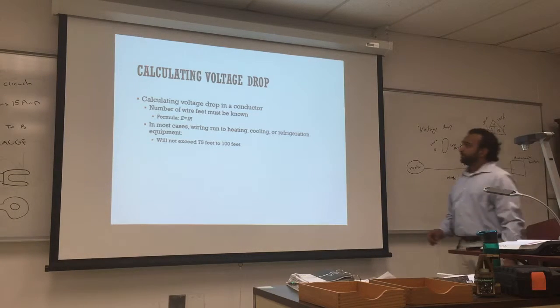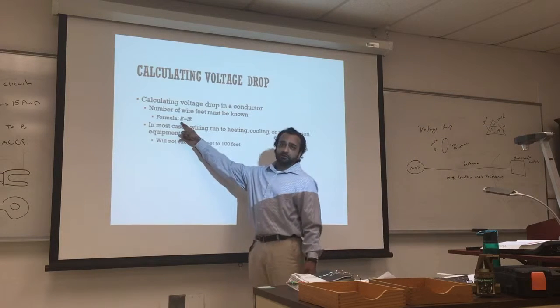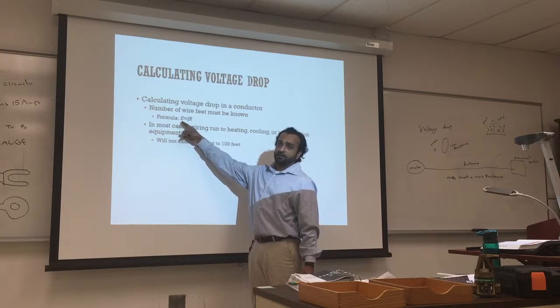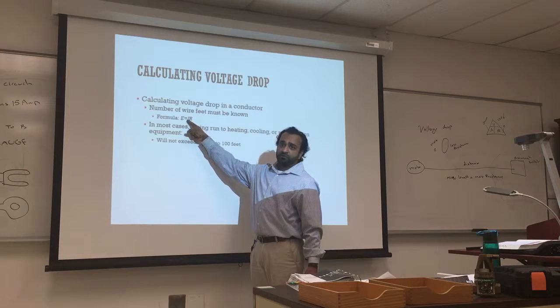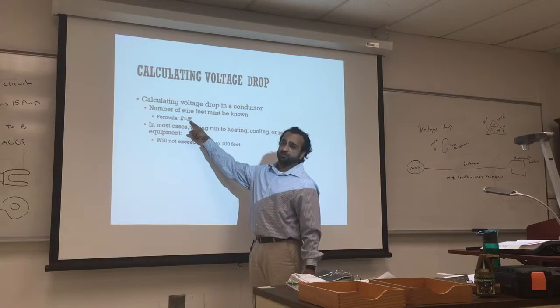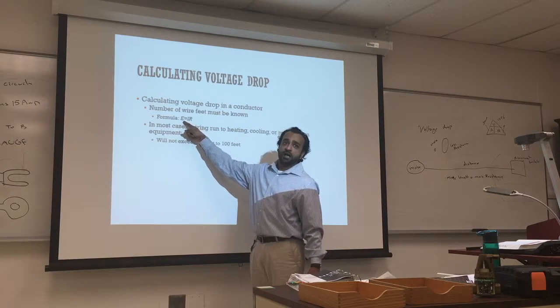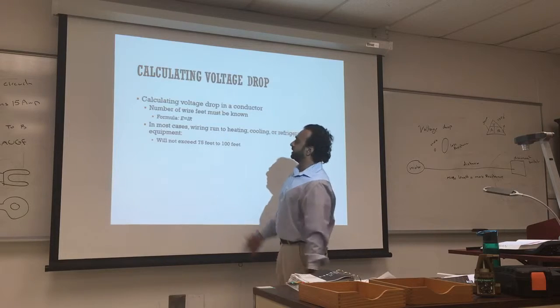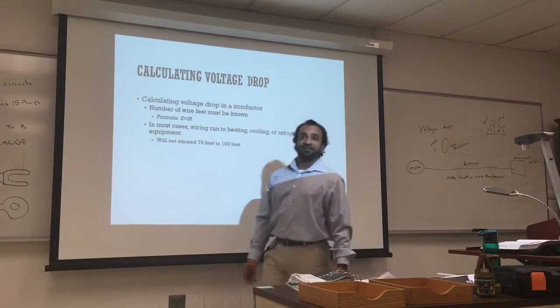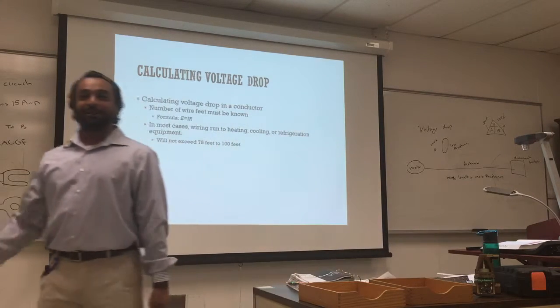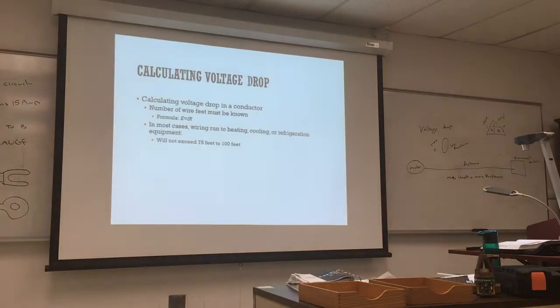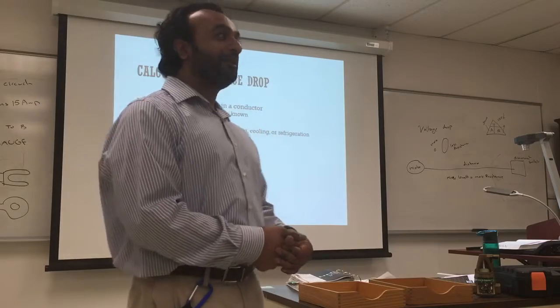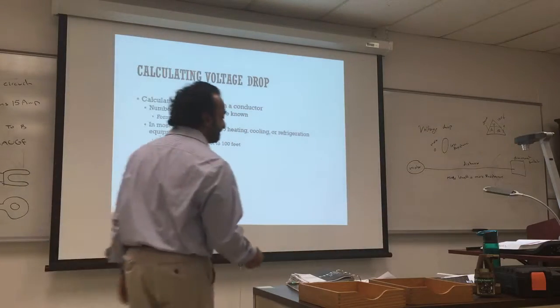So the voltage drop will be: the amperage required for the equipment times the resistance of the wire, and that will give you the voltage drop, which you subtract from the incoming voltage. Or you can do it the easy way - connect the wire, measure the voltage at the beginning, and measure the voltage at the end. What am I getting, and see what my voltage drop is - am I getting 10% or not?